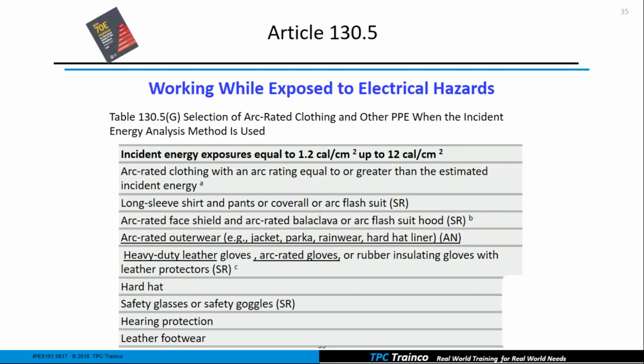And it goes on. Also, this is a nice change in my opinion here, 130.5G, a table that actually came from Annex H of the 2015 version of 70E. So this used to be in the annex. Now it's in the regular sections of 70E. And what they have done here is they have given us the personal protective equipment that we need if we are using the incident energy analysis method. And of course, that's the full-blown arc flash study. So if we're doing the full-blown arc flash study, it now tells us exactly what we have to wear, all the way up to 12 calories.